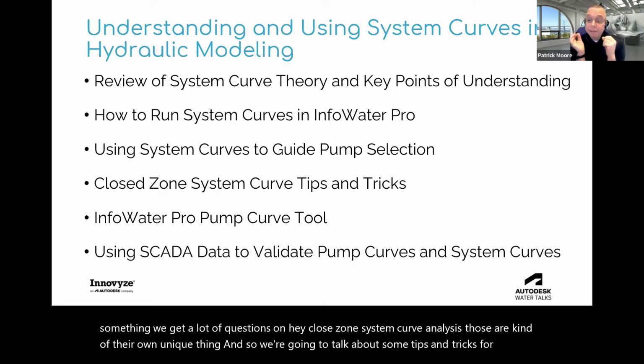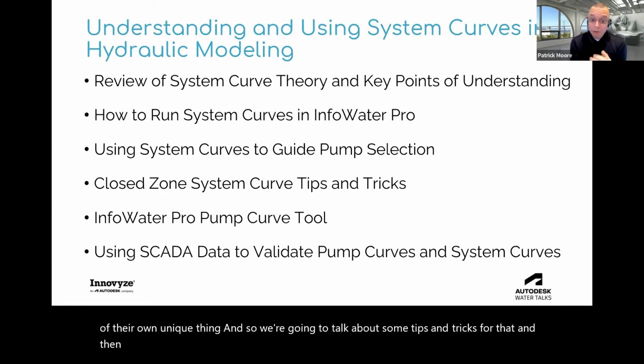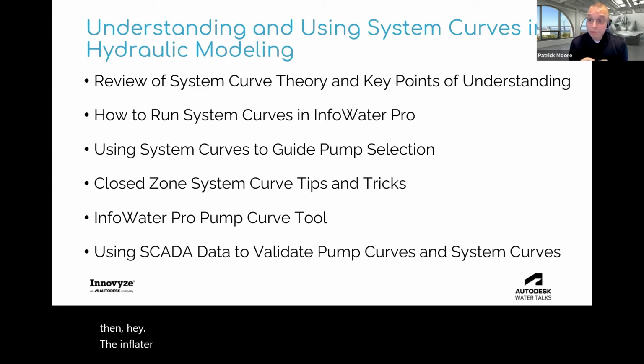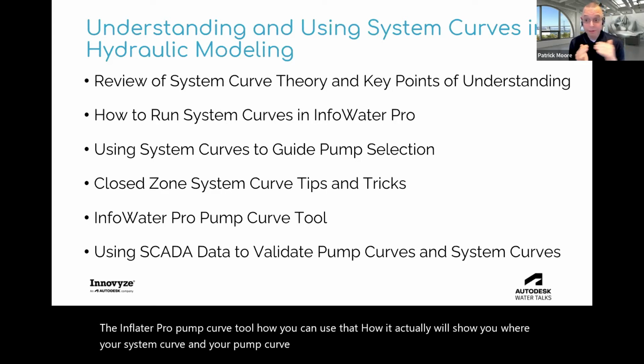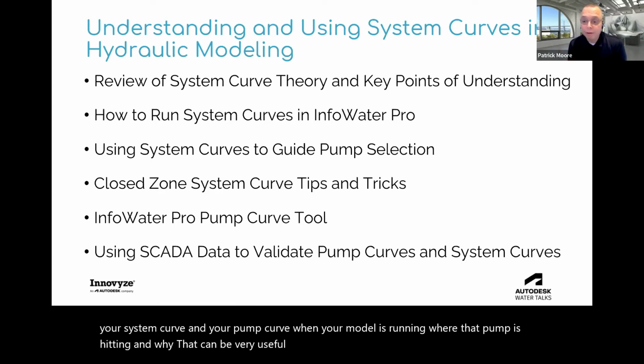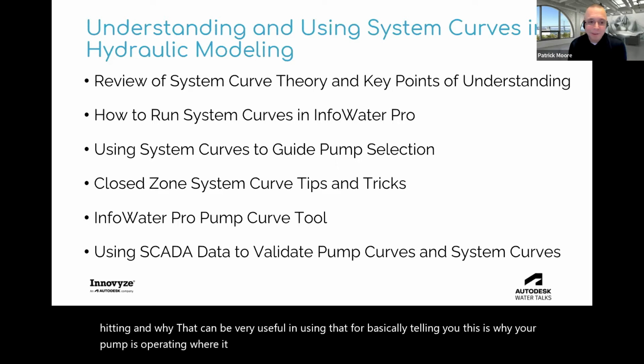And then the Infowater Pro pump curve tool, how you can use that, how it actually will show you where your system curve and your pump curve are, when your model is running, where that pump is hitting. And why that can be very useful for telling you, this is why your pump is operating where it is. We'll get into that later on.